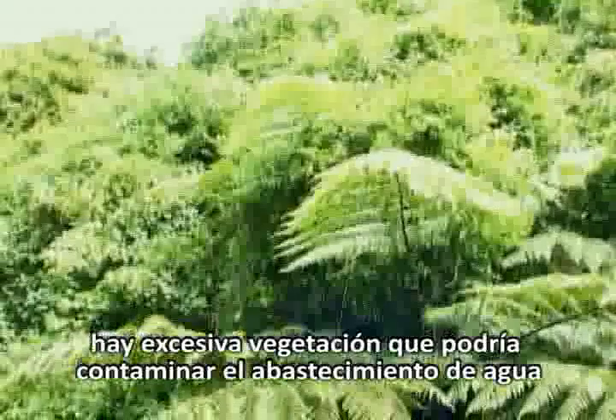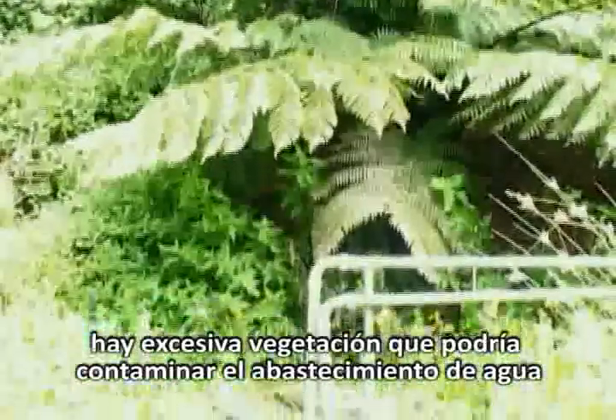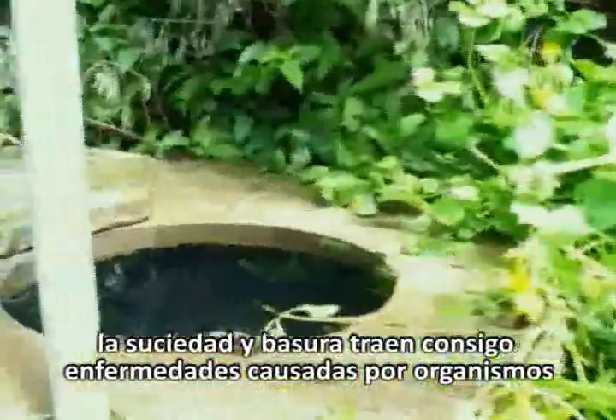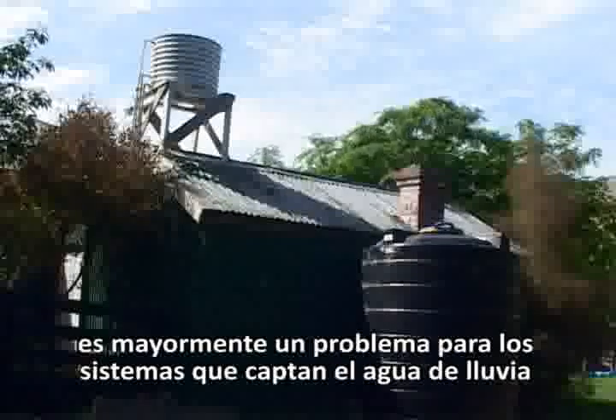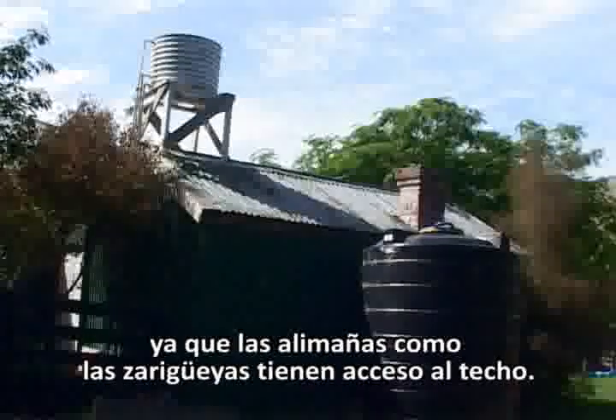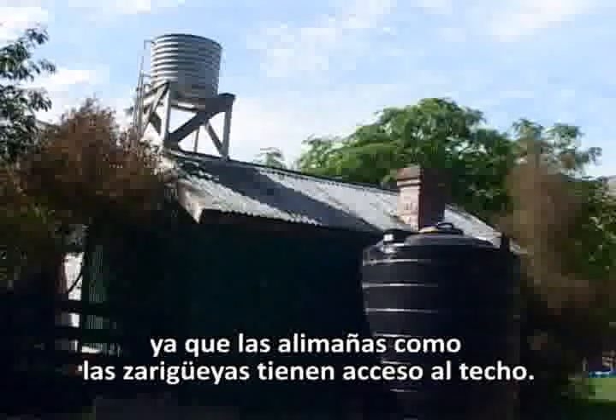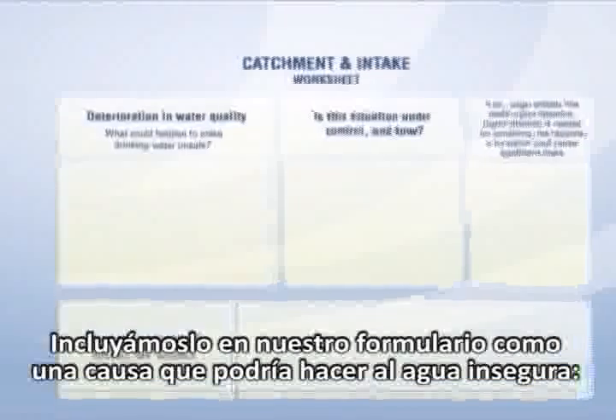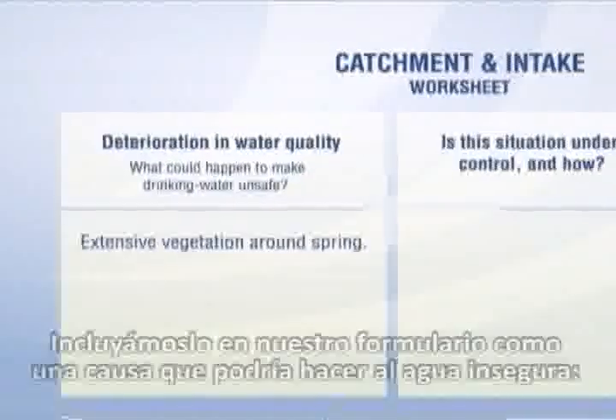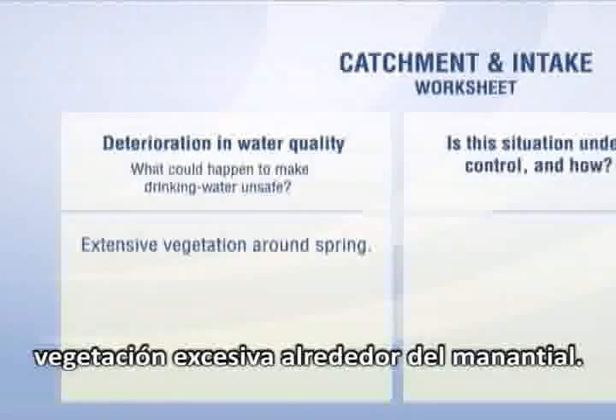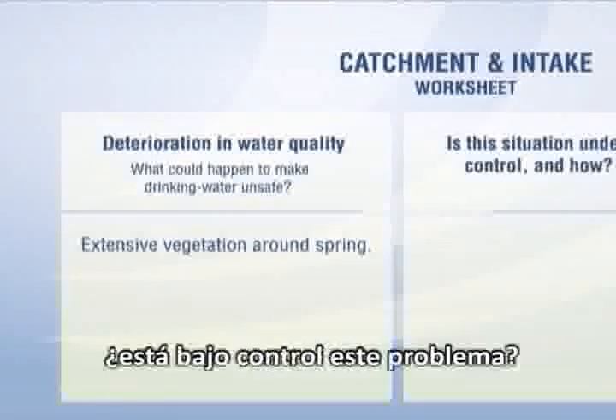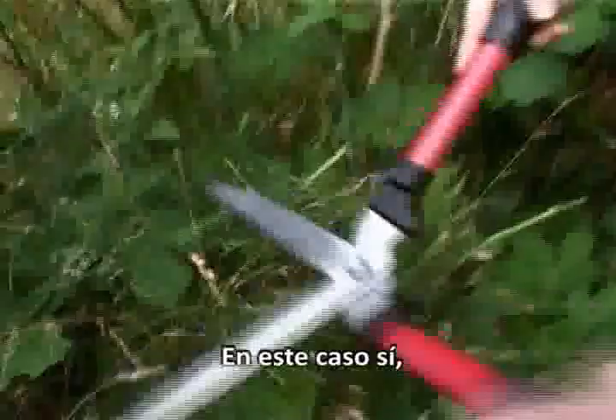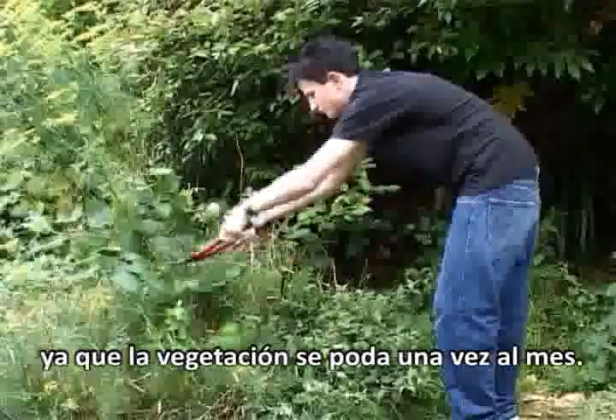At this spring, there is extensive vegetation surrounding the spring that could contaminate the water supply. Dirt and weeds carrying disease-causing organisms could enter the supply and really deteriorate the water. Overhanging vegetation is more of a problem for rainwater supplies, providing access to the roof for vermin like possums. Let's add that to our worksheet as a cause that could make the water unsafe: extensive vegetation around the spring. Now, is this issue under control? In this case, yes, as the vegetation is now being cut back once a month.